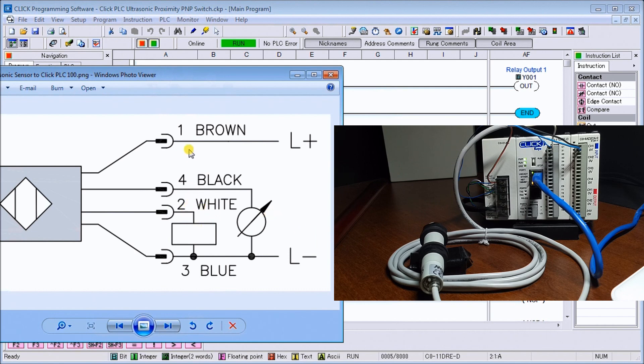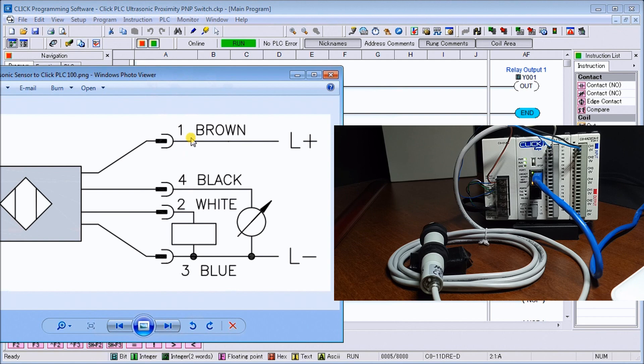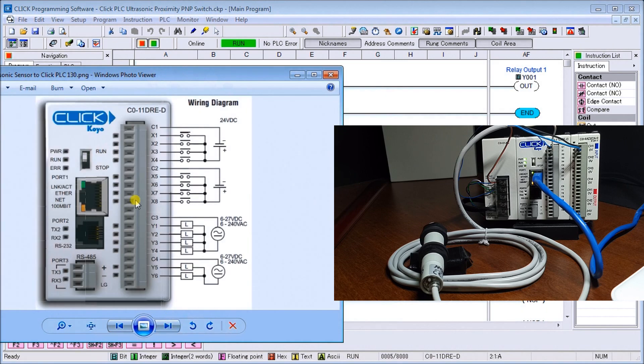That's my wiring diagram, and because you can see that we're actually pulling it up to the positive voltage, this is positive switching or sourcing a load or PNP style switching for your PLC.